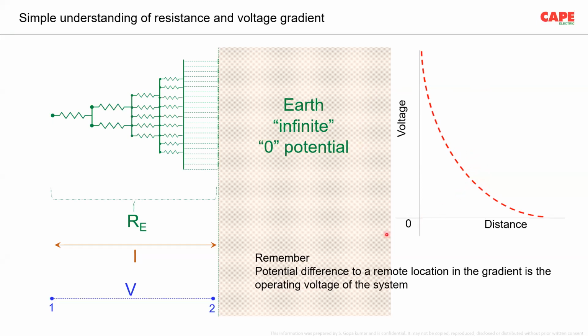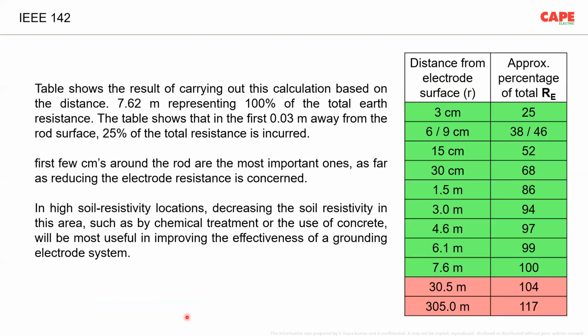Now, however, for a high voltage system, of course, depending upon the operating voltage, the voltage is fatal. As a result, step and touch voltages can happen. Now, for example, you think that this voltage gradient is made at a distance of, let us say, 10 meters. If somebody asks, do you think that in a typical place, the 100% earth resistance is within this sphere of influence of 10 meters?